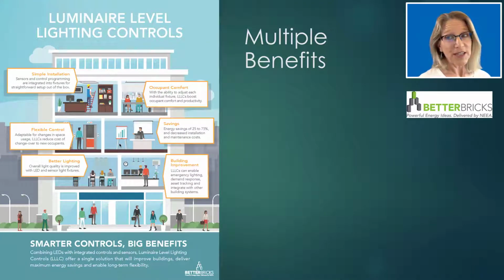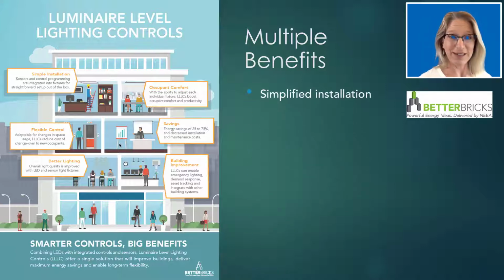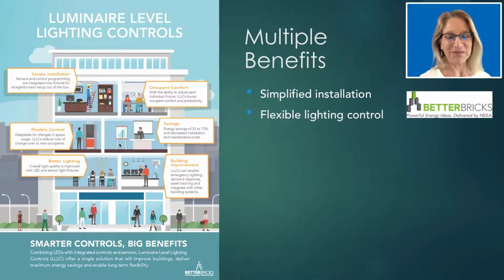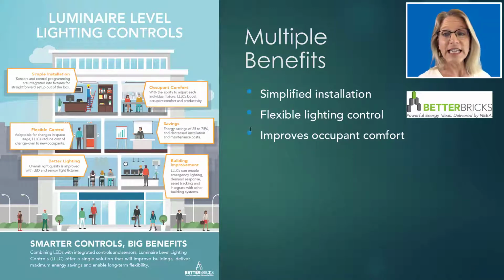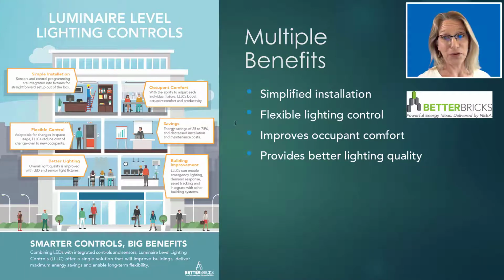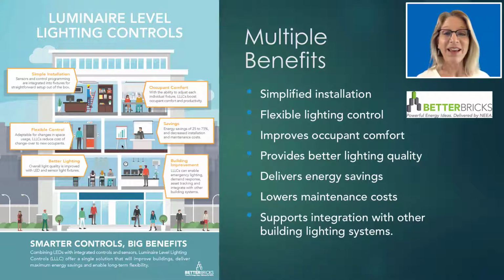So in summary, Luminaire level lighting controls provide multiple benefits in a variety of ways. Sensors and control programming are integrated into the fixtures for straightforward setup that simplifies installation. Flexible controls reduce the cost of space reconfiguration. The ability to adjust each individual fixture can improve occupant comfort and productivity. Studies have shown that people perform better when they have more control over their personal environment. Lighting quality is improved by adjusting light levels to the preferred level based on the surrounding light sources, including daylight. Demonstration projects have reported from 25 to as high as 75% energy savings compared to standard lighting controls, and it offers reduced maintenance costs. In addition, LLLC supports integration with other building lighting systems.